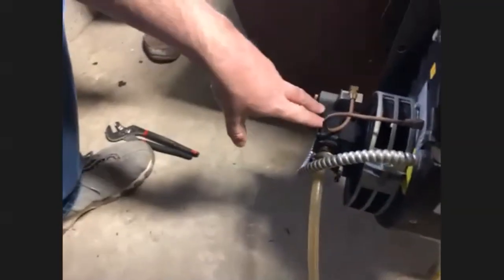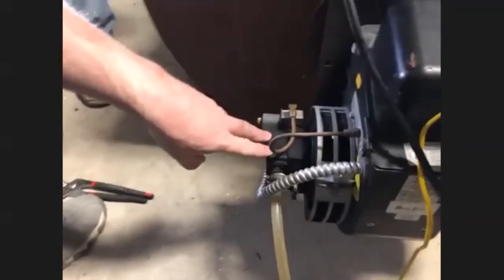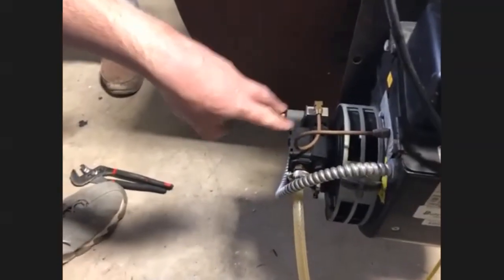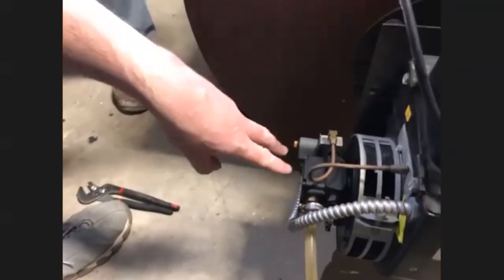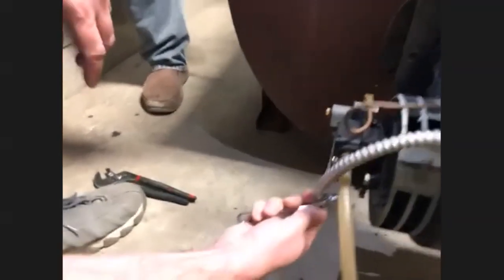If you have issues that you need to verify, if there's fuel, if the pump is not working properly, or you think you may have run fuel out, do not run these fuel pumps empty. You do not want them dry. It will destroy the pump itself. You must have fuel in it all the time.